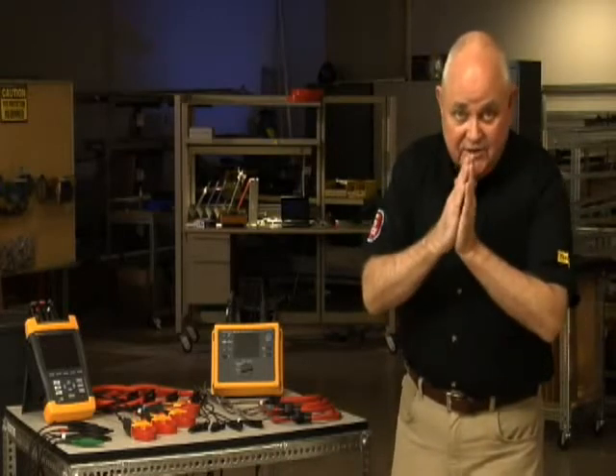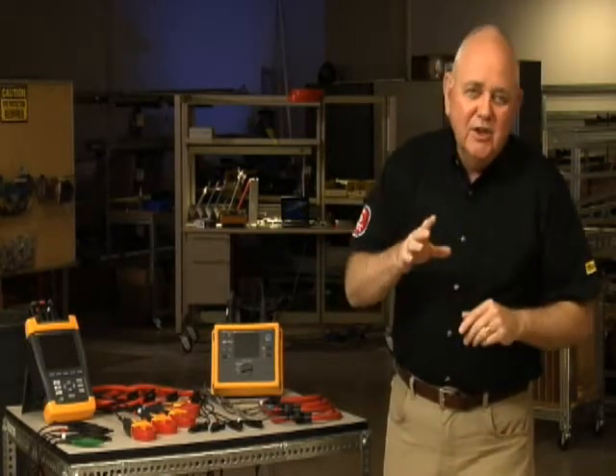In this video, we're going to talk about transformer problems. Now, we're all familiar with 60-cycle hum in a transformer, the vibration of those steel laminations in the core at 60 cycles per second. But if that transformer starts to buzz and overheat, you've got problems. The good news is finding the culprit may not be that difficult.